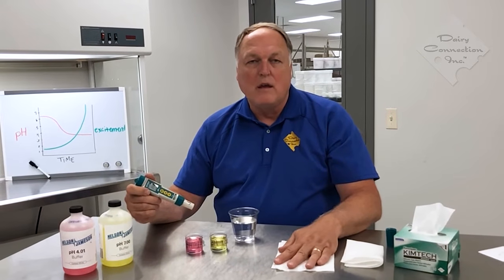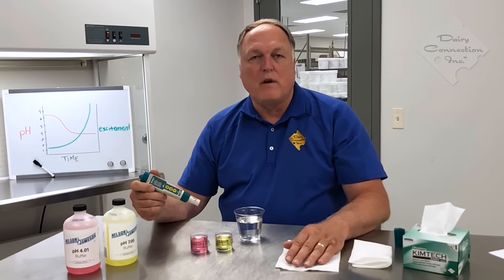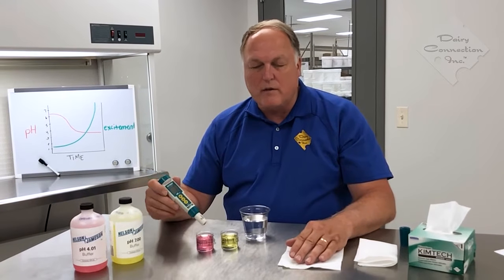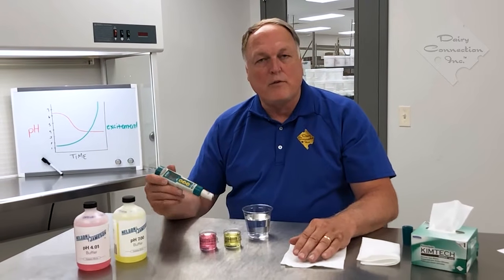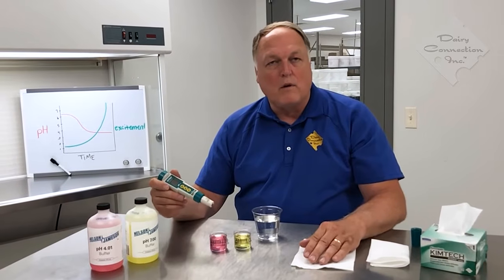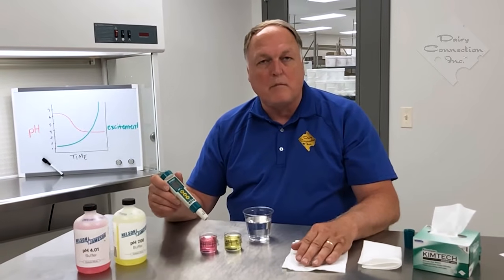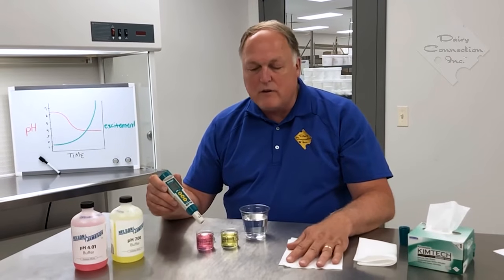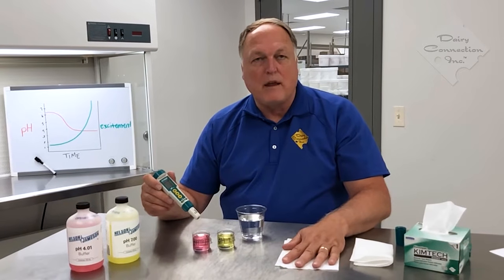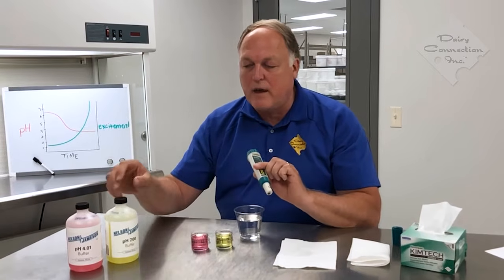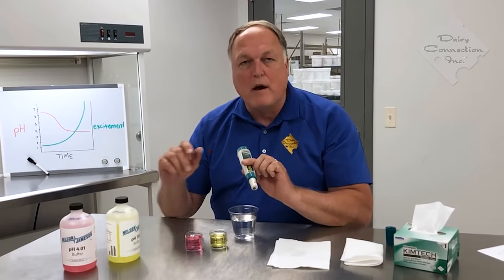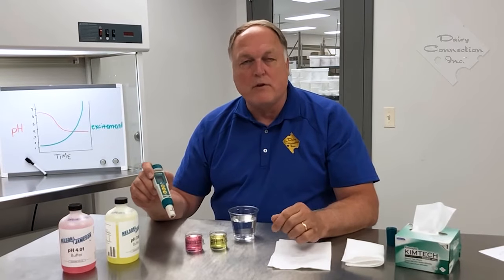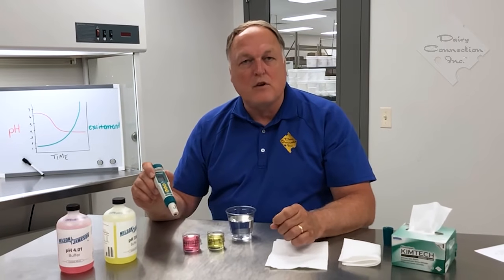So I want to review some of the common errors that people have with the pH meters that we hear often. And a lot of it is just understanding what it is you're doing. The first one is proper calibration. I went through the techniques of how to calibrate. One of the things I want to mention is the pH buffer solution should be fresh. It does have an expiration date, so when you purchase these standardized solutions, make sure you monitor when that pH buffer solution will expire. It does go weak, and if it goes weak, then your calibration will not be accurate.